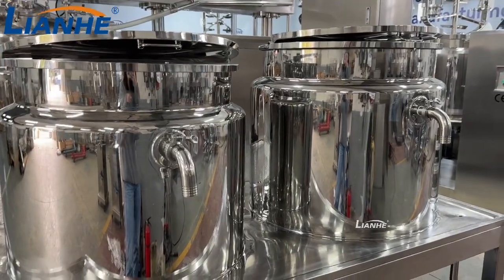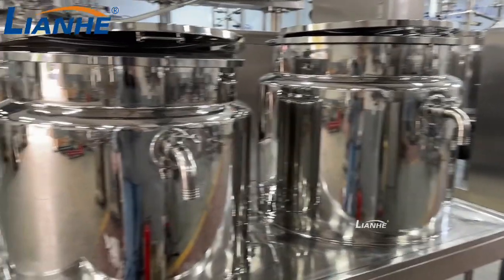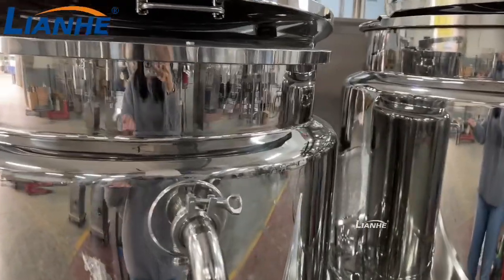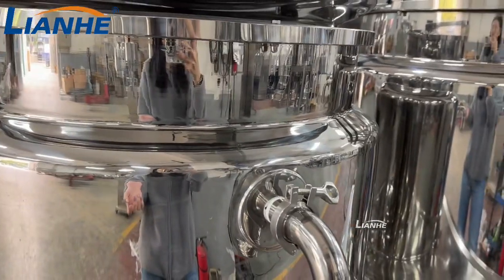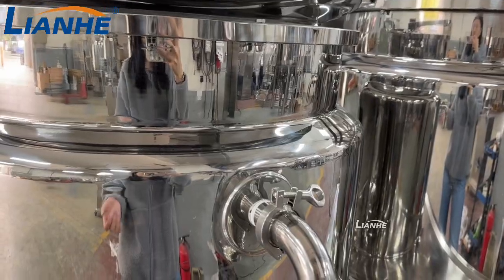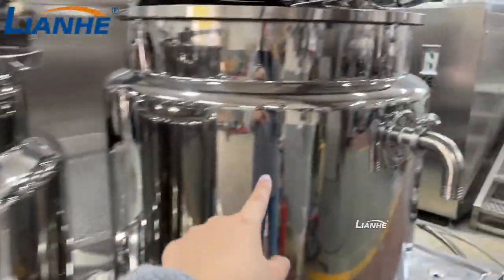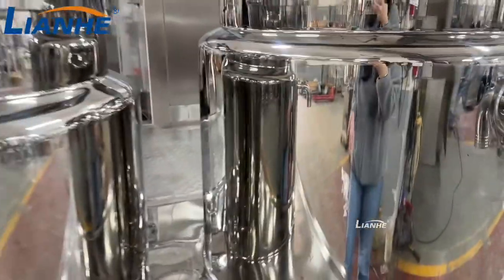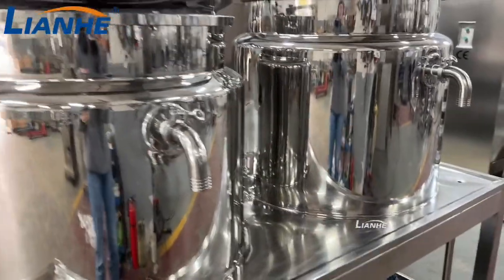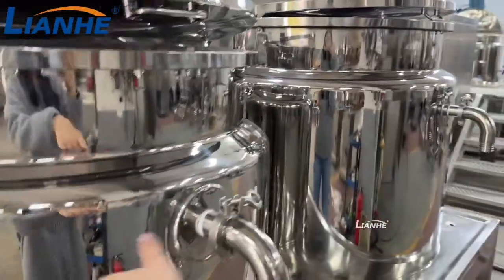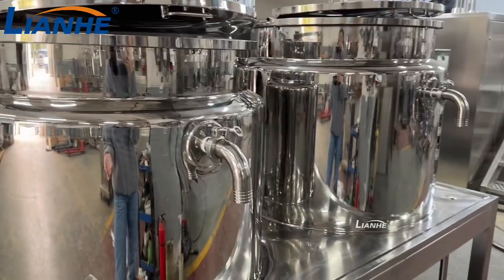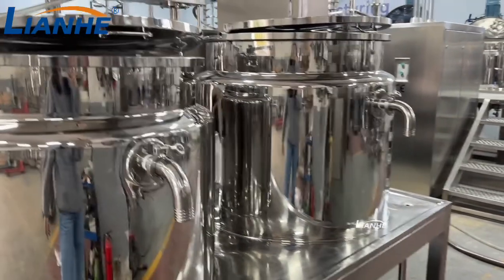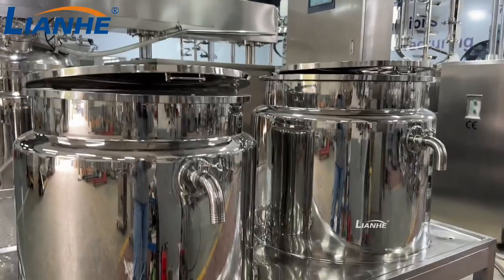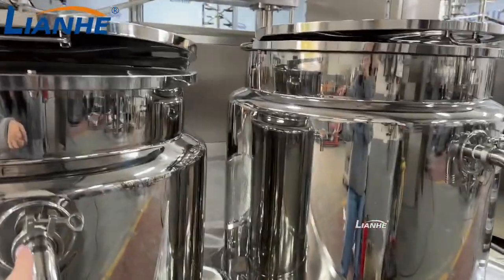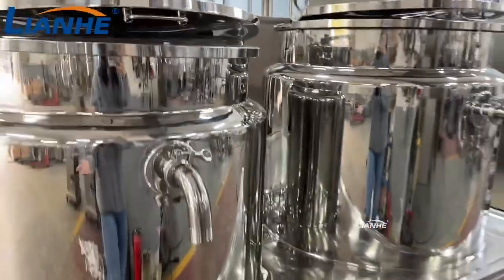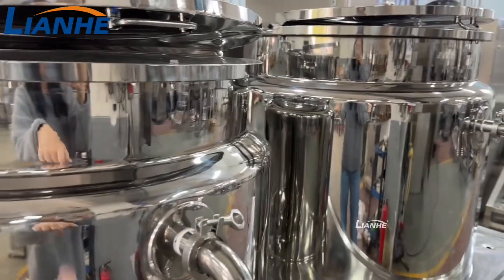And then for the oil tank and water tank, our engineer has already put the thermal oil, that means the heat transfer oil, inside the jacket of these two tanks. So you don't need to put the water inside these two tanks' jackets. You can directly use the heating function of these two tanks. Remember, do not put the water inside these two jackets, otherwise the tanks might have safety problems.